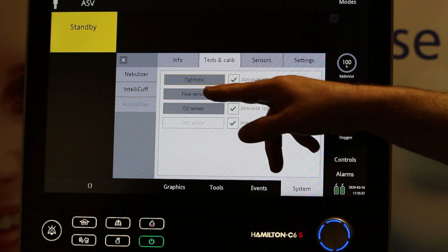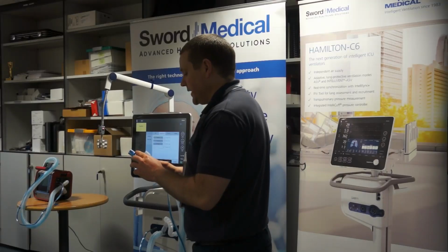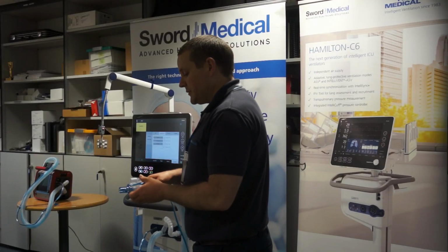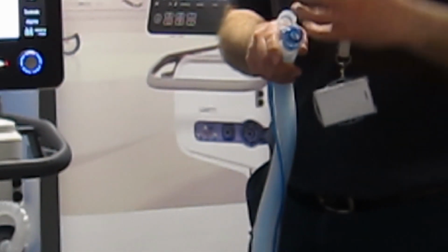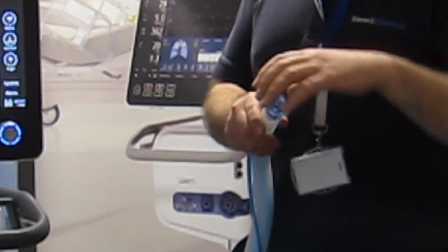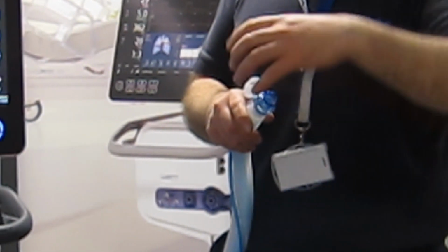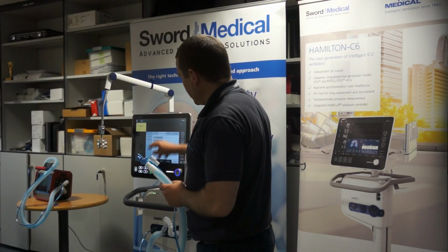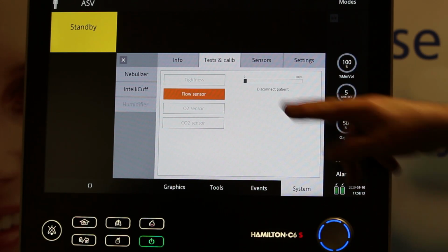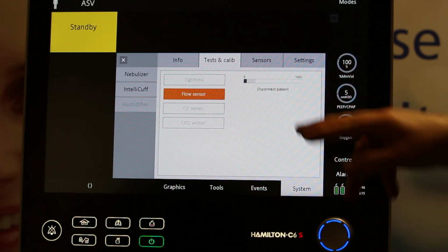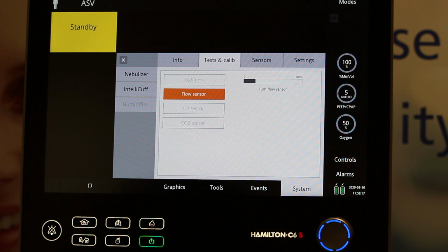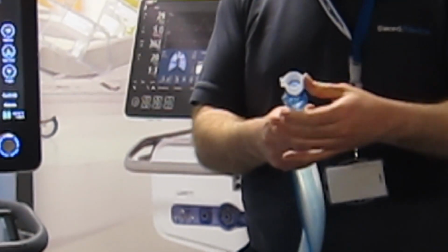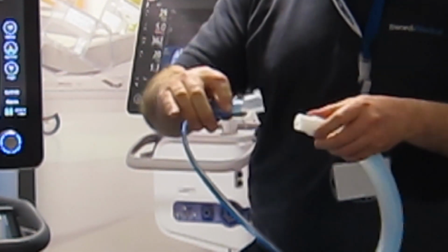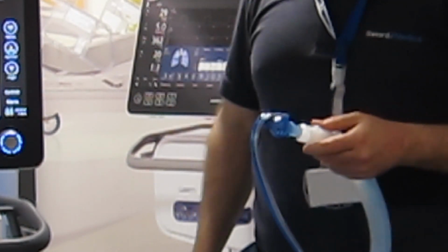The next one I'm going to do is flow sensor. So this is the flow sensor. You get a sizing adapter with every circuit mounted on the flow sensor here, and that allows me to turn the flow sensor during calibration, so the ventilator is able to blow air over it in both directions, and I'll show you how that works. So I hit flow sensor, it tells me to disconnect the patient, and the first thing it prompts me to do is to turn the flow sensor. So using my sizing adapter, you plug it onto the sensor like so. It allows you then to turn it around and plug it onto the circuit.